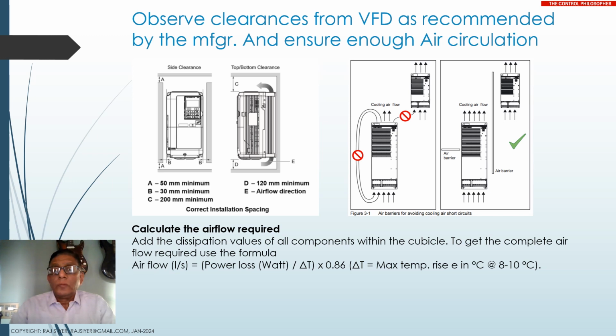Okay, now when you get a VFD and want it to be installed inside a control panel or an MCC, you have to observe the clearances. They will say that you have to leave some 3 inches, 4 inches above and below the VFD. Sometimes they may say you need not give much side clearance, you can stack them side to side. Whatever it is, you have to see what the manufacturer wants, and especially where the VFD's cooling fans are located.